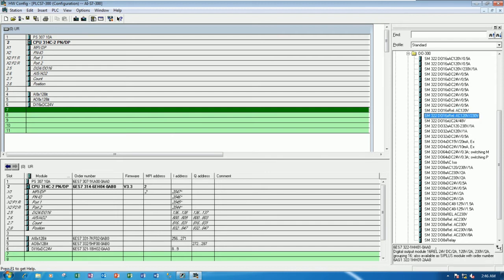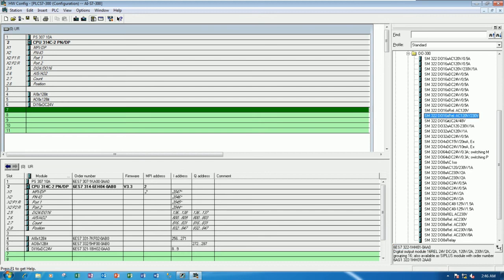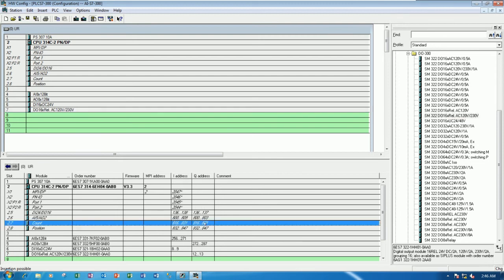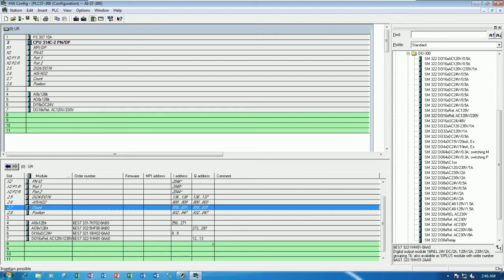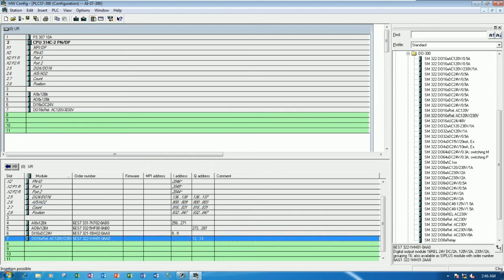So this one, let's see here is the model number or serial number. So we can drag and drop this module to the rack. And the address will start from Q12.0 until 13.7. Totally 16 bits also.